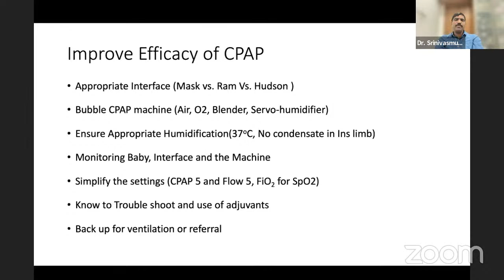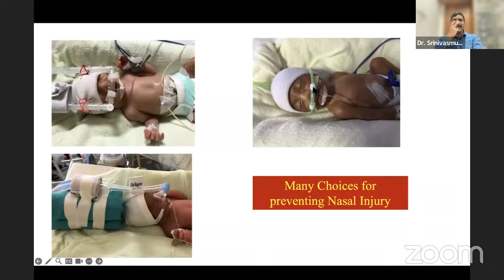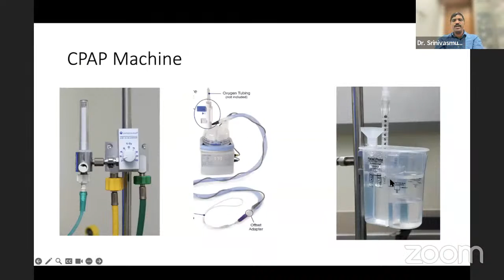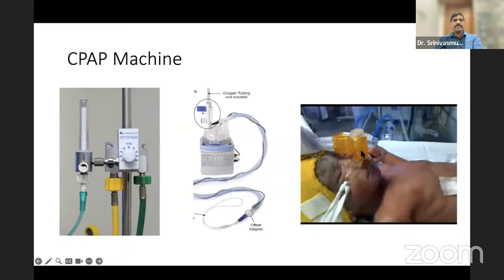So whether it is Hudson prongs, Drager mask, or Ram's cannula, all are good choices. Only choice you have to understand is in Hudson prongs and in Drager mask, there should be a snugly fitting, no leaks around the nostrils. But in Ram's cannula, it should not snugly fit. There should be 80% fitting. There should be some amount of leak around the nostrils. Good CPAP machine should have a blender, compressed air, compressed oxygen, a flow meter, a good humidifier, and a pressure generator like a bubble CPAP generator. So in flow drivers, the bubble generator is replaced by an interface which delivers a pressure at the interface.